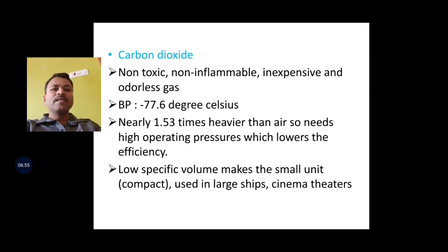Next, carbon dioxide is a non-toxic, non-inflammable, inexpensive and odorless gas. Boiling point is minus 77.6 degrees Celsius. It is nearly 1.53 times heavier than air. It needs high operating pressure, which lowers the efficiency. Okay, operating pressure increases means efficiency will decrease.